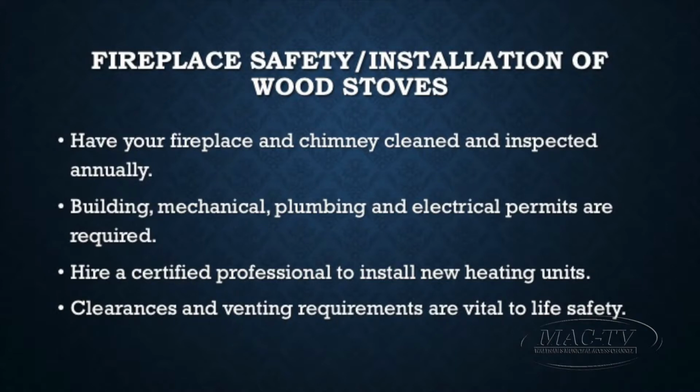You want to have it cleaned by a licensed chimney company. They'll come in, they'll scrape all the creosote off the sides of the flue. They'll check the dampers. They'll make sure that everything's functioning and lubricated well, and that there's no creosote buildup. That's the number one cause of chimney fires, is the buildup of creosote. I don't know how well those creosote burning logs work. I would not rely on them. I would definitely have a company come in and inspect and clean your masonry chimney once a year.